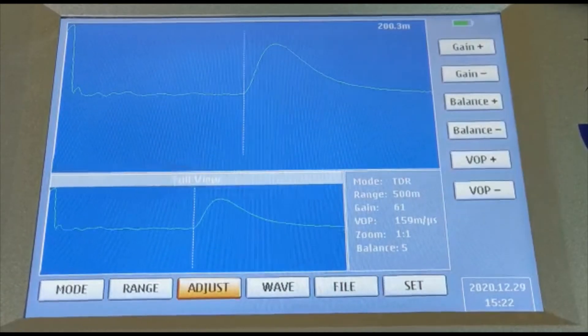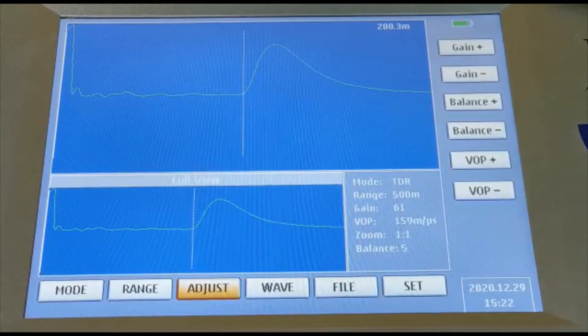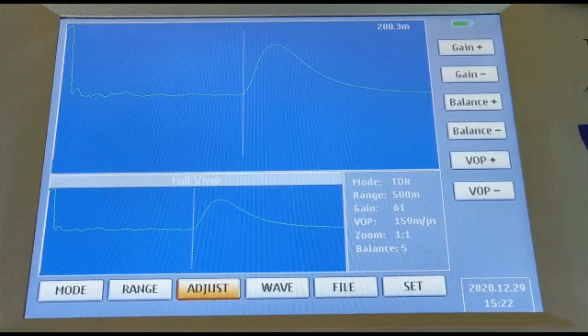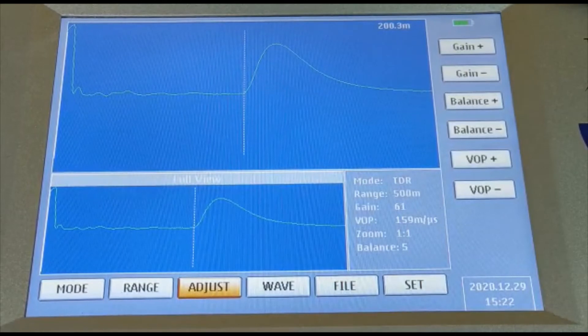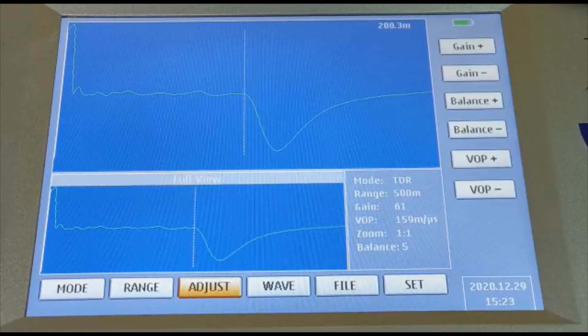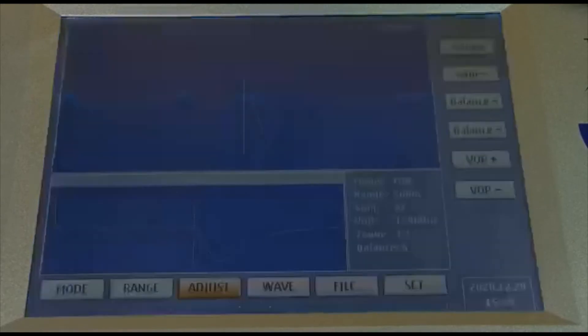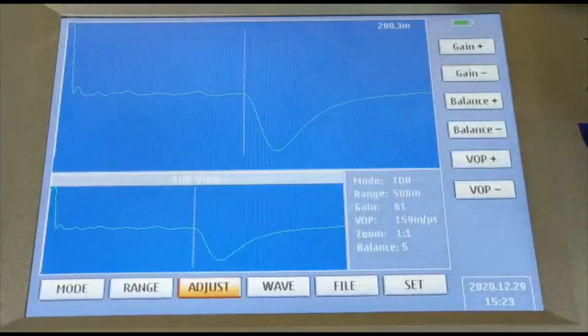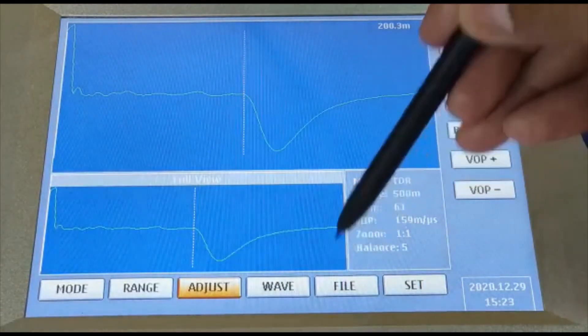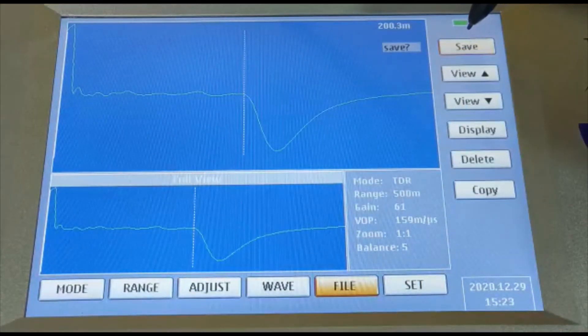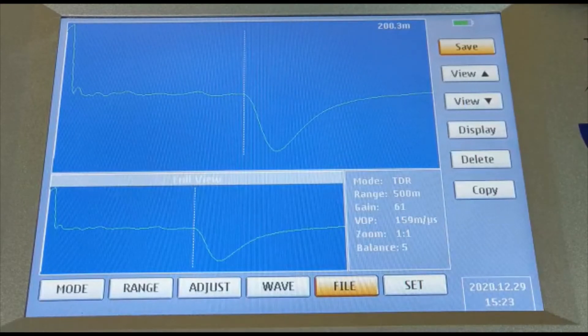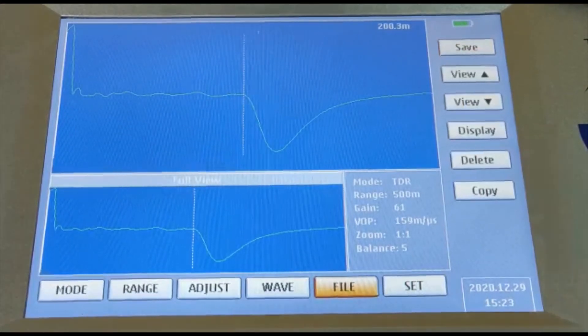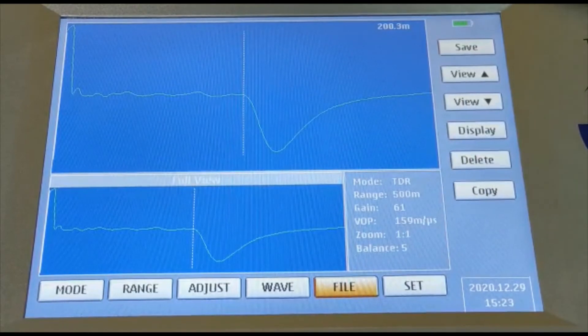Now I create a short circuit fault at the end of the line and we will see how the graph reflects it. I have made a short circuit there and I press test — you can see that the curve has changed, showing it as a short circuit fault at the end of the line. We go to file and save it, recording the waveform.